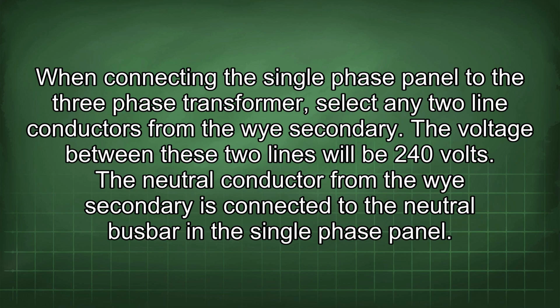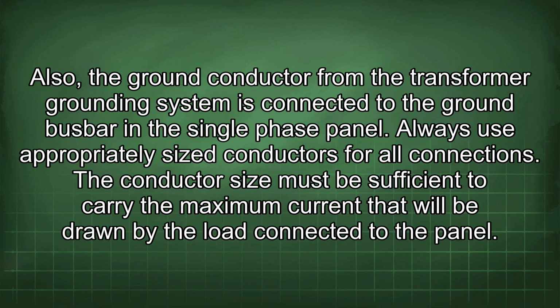The voltage between these two lines will be 240 volts. The neutral conductor from the Y secondary is connected to the neutral busbar in the single-phase panel. Also, the ground conductor from the transformer grounding system is connected to the ground busbar in the single-phase panel.